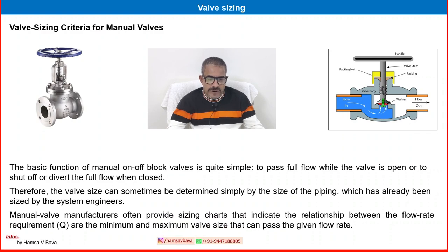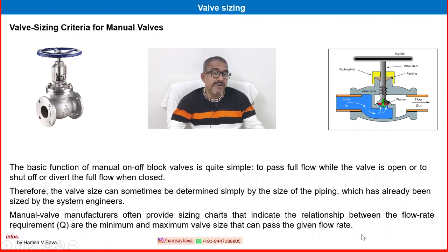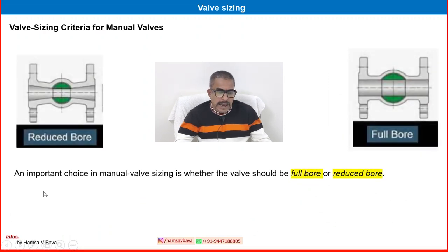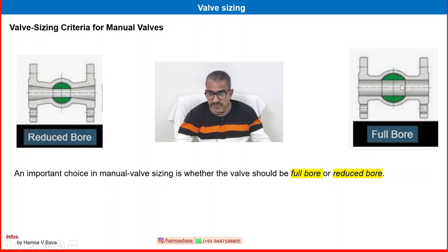Manual valve manufacturers often provide sizing charts indicating the relationship between flow rate requirements, and the minimum and maximum valve size that can pass a given flow rate. An important choice in manual valve sizing is whether the valve should be full bore or reduced bore. In full bore, the valve diameter is equivalent to the pipe diameter, while in reduced bore, the valve sizing is slightly less than the pipe diameter.